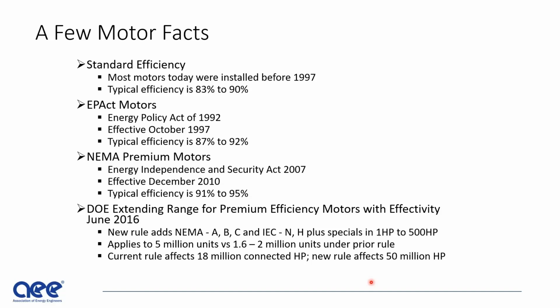The Department of Energy extended the range for premium efficiency motors with effectivity in June 2016. What they decided was that trying to go from 95 to 98% was a fool's errand. It's just not going to work to try and up the efficiency even more. What they did instead was include a broader class of motors in the category for premium efficiency. And you can see the new rule adds the NEMA class A, B, C, the IEC N and H class, and we're going up to 500 horsepower now, where it was only 200 horsepower before.